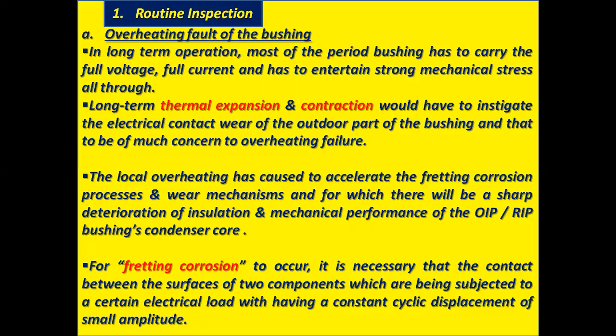The local overheating accelerates the fretting corrosion process and wear mechanisms, and there will be a sharp deterioration of insulation and mechanical performance of the oil impregnated paper or resin impregnated paper bushing condenser core. For fretting corrosion to occur, it is necessary that the contact between the surfaces of two components is subjected to a certain electrical load with a constant cyclic displacement of small amplitude.